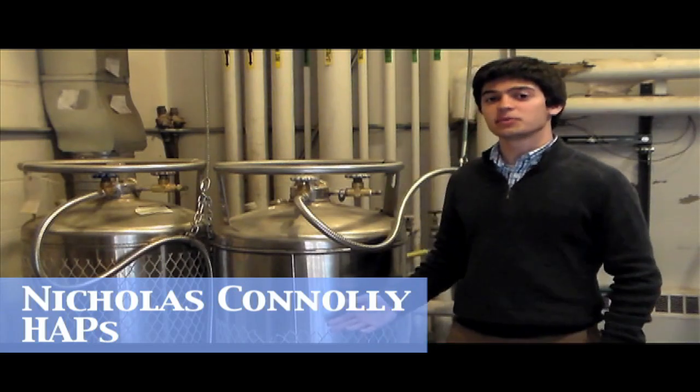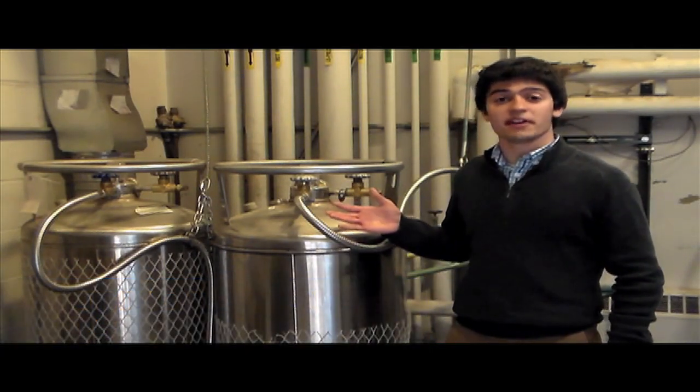Safety was of utmost importance with the design of the UniPump. Tanks are rated NEMA 7 explosion-proof, lines are anti-static, fail-safe valves prevent backflow, and all components of the system must be secured before fueling can begin. A gas monitor is also installed to detect leaks, and if the leak approaches the lower explosive limit, it automatically shuts down the whole system and a small gas removal system turns on.